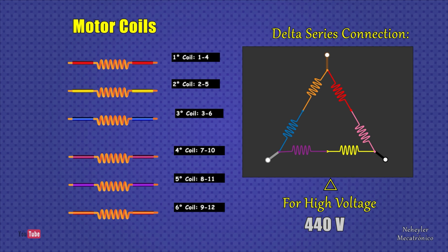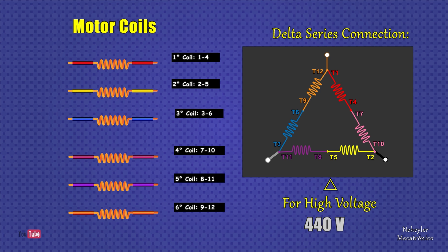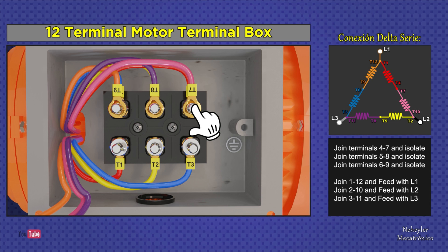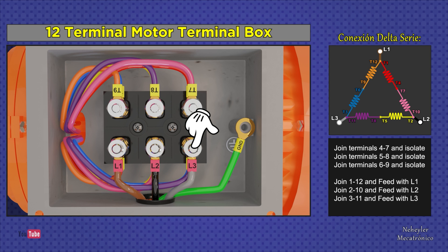Now let's see the series delta configuration, which is used for high voltage. In this configuration, the coils that make up each side of the triangle are connected in series. Clockwise, we have terminals 1 and 4 of the first coil, 2 and 5 of the second coil, 3 and 6 of the third coil, then 7 and 10, 8 and 11, 9 and 12. Terminals 1 through 6 must be placed in the motor terminal box as shown. Then join terminals 4 and 7, join 5 and 8, join 6 and 9. Also join 1 and 12 to feed L1, join 2 and 10 to feed L2, and join 3 and 11 to feed L3.